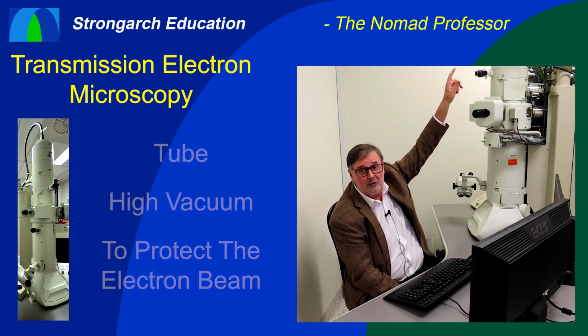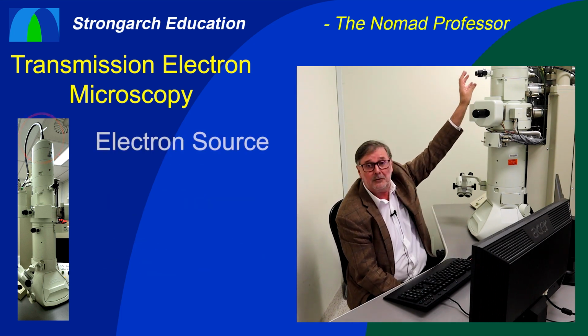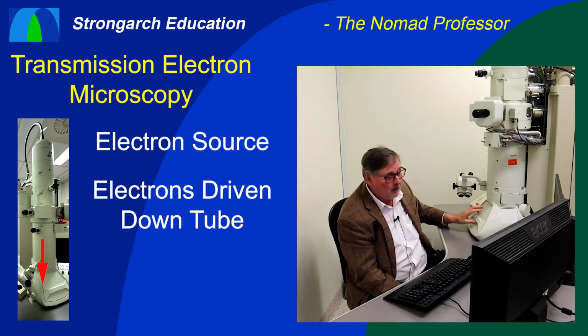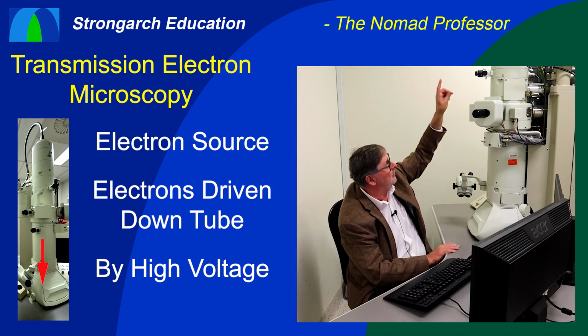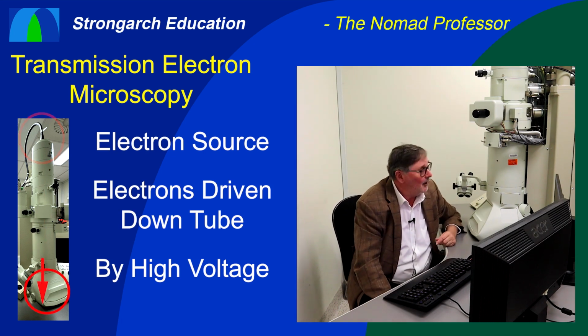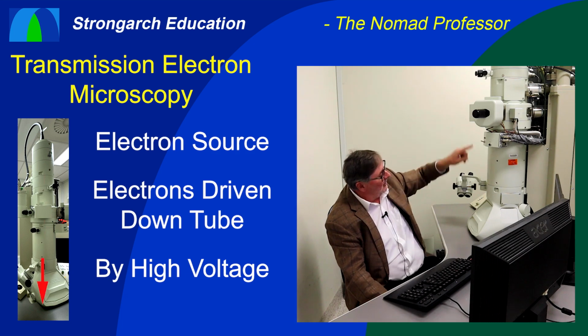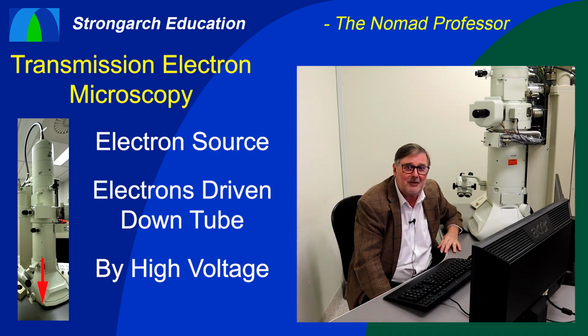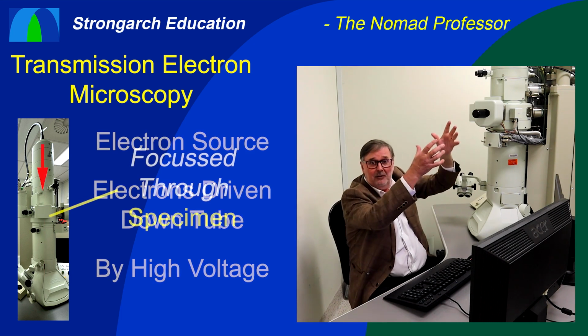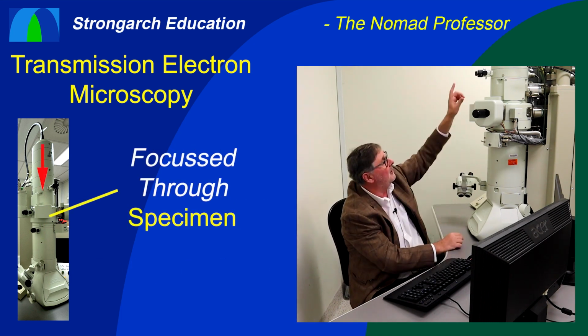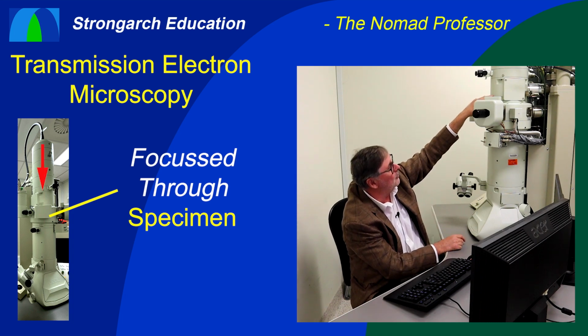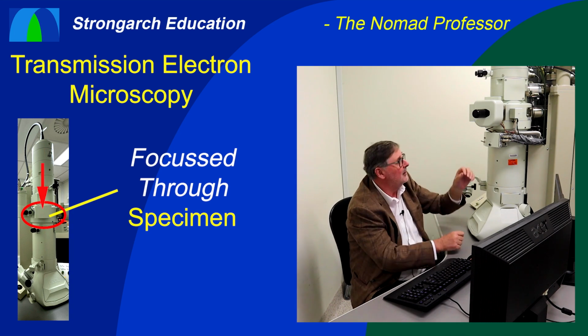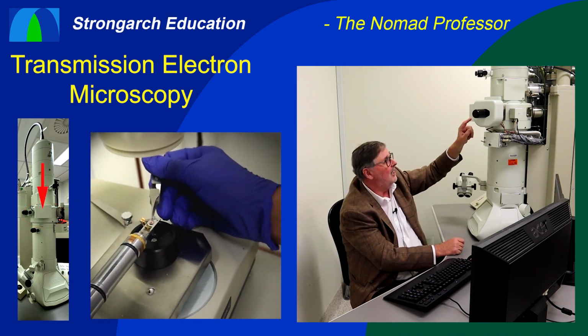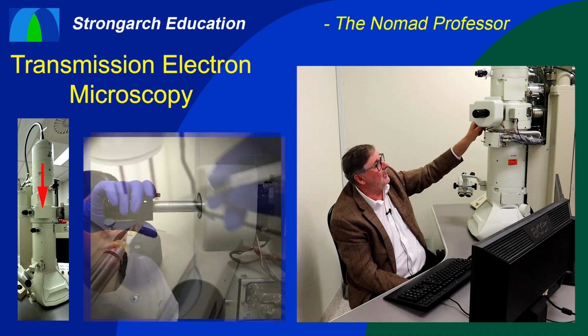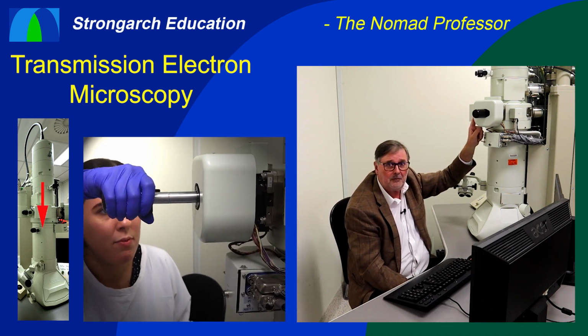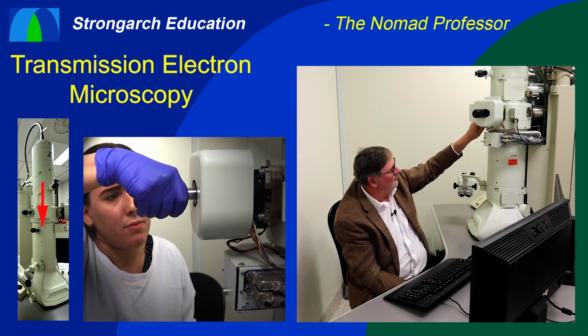So at the very top of the column, there's a source of electrons that is driven down through the column by a high voltage that's kept between the top and the bottom of the electron microscope. So electrons are being fired down from the top towards the bottom, and on the way it's being focused. This electron beam is being focused by magnetic lenses that are in the top part there, first of all through the specimen, which is held in place by a special little specimen holder that enters the electron microscope through this portal, through this hole. The electron beam then fires down through here.